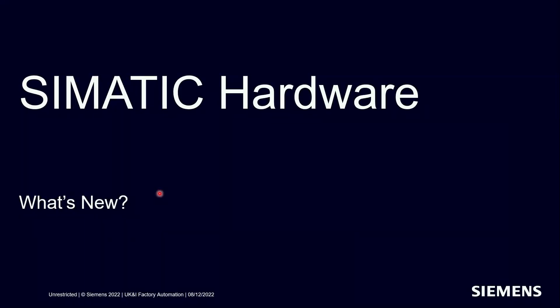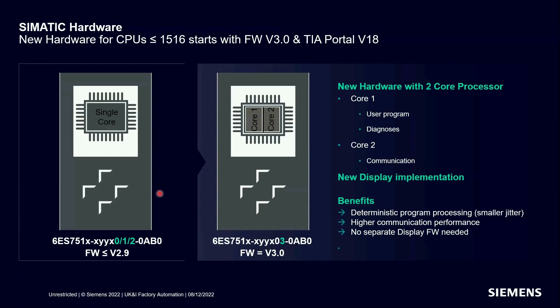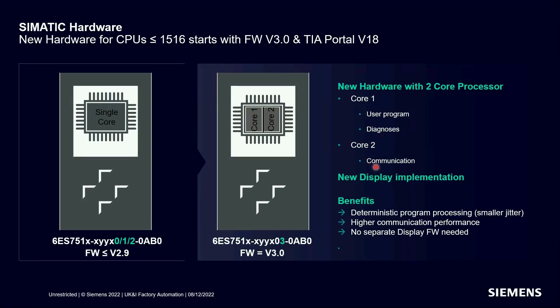We wanted to quickly run through some new introductions to the Simatic hardware portfolio. It's around 10 years since the S7-1500 was launched, and it's about to go through an innovation cycle. Firmware will be updated to version 3, and there will be a hardware release for CPUs between the 1511 and 1516, switching to a dual-core ARM-manufactured CPU. Core one processes the user program and diagnostic events, and core two handles communication tasks.